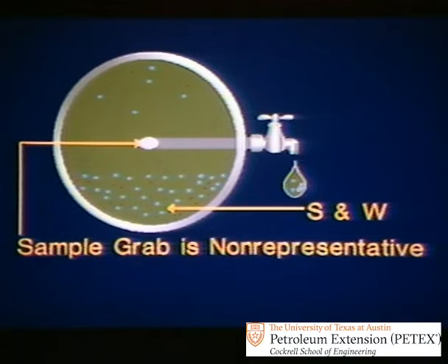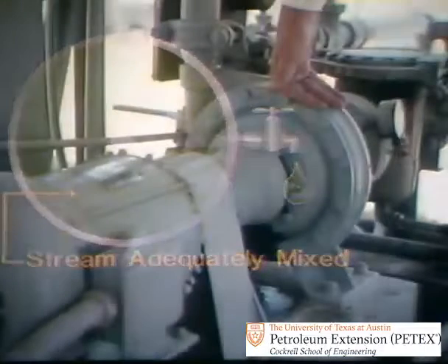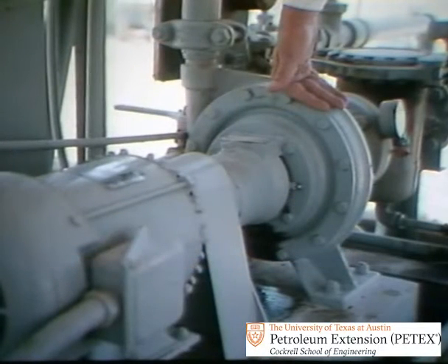Now, to solve this problem, the stream must be adequately mixed. But how can the stream be mixed? Well, in several ways. For example, a pump can cause the stream to mix. So, a sampling point located just downstream from the pump may give the needed mixing.